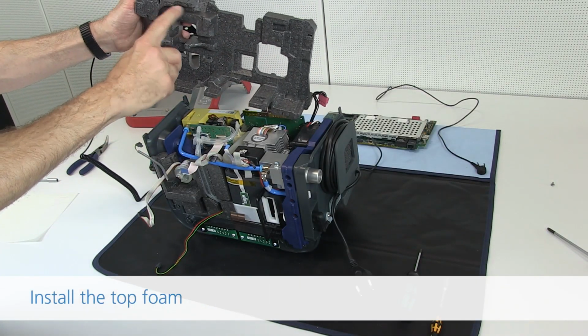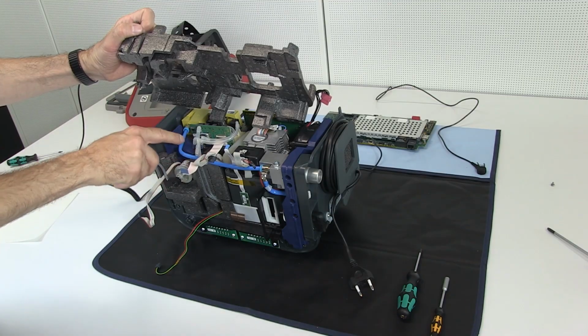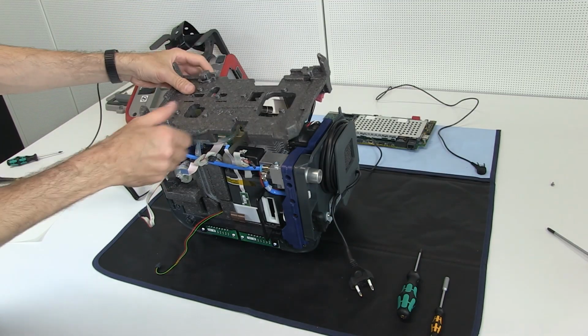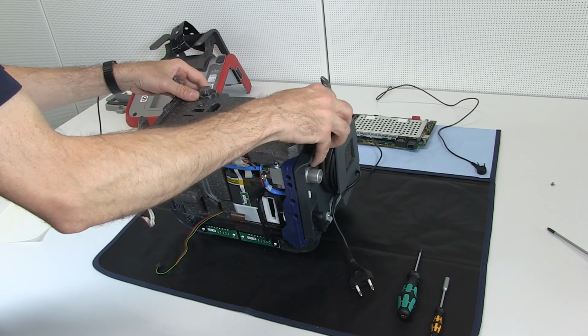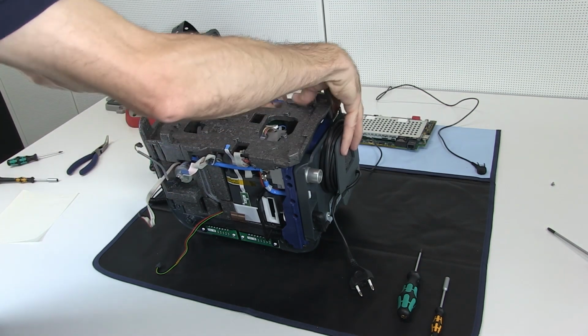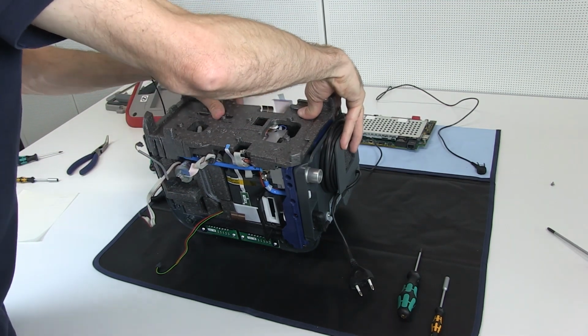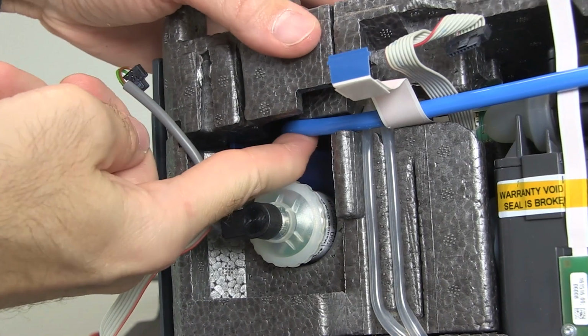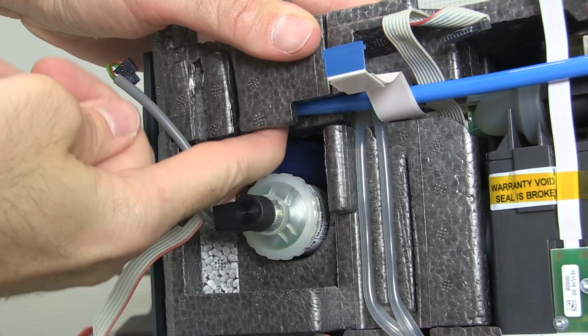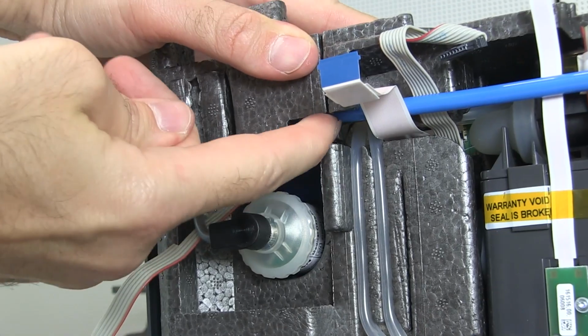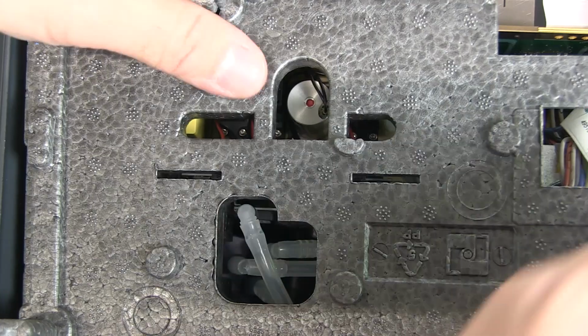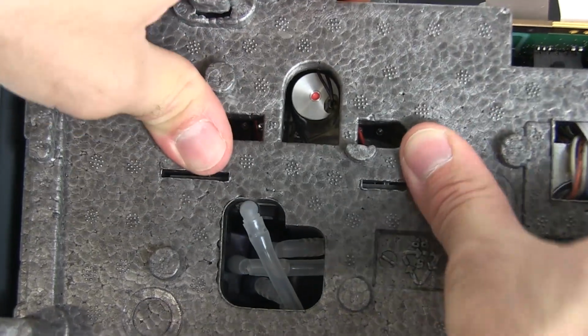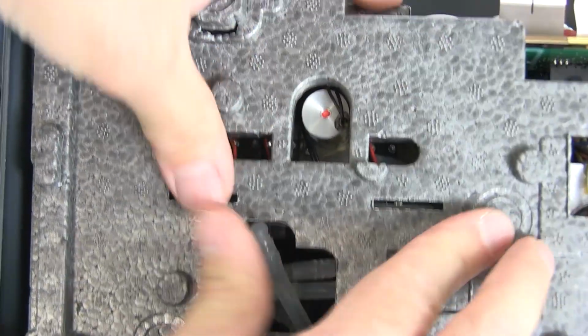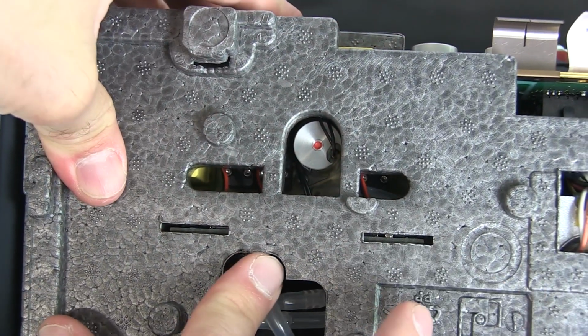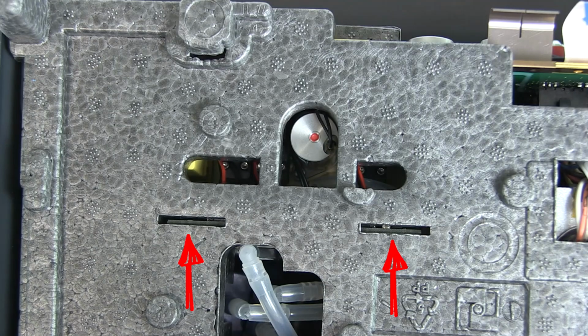Install the top foam. Locate the groove in the foam for the nebulizer tube, then push the nebulizer tube inside the groove. Make sure that the pressure sensor assembly board is positioned correctly below the top foam and that the PX valve tube from the expiratory valve is still connected to the port on the pressure sensor.